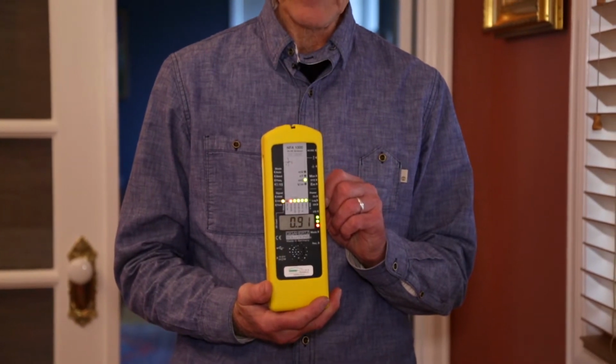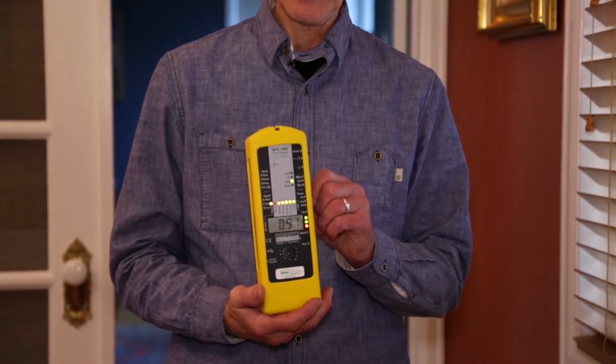We also will see in a second that this is rather pervasive. I mean, this one error, because it's splitting the current flow and it's going on several different neutral return paths, can affect large amounts of the house, depending on where the cables run that those neutral return paths are in. So we have a similar thing in the dining room too. So let us take a look over at that area. So we've arrived in the dining room, and we're looking at a field level of 1.8 milligauss here in the dining room. So not as bad. It's nearly at the level we would consider to be acceptable, but still being affected by this, because when the load is gone, then this is gone.